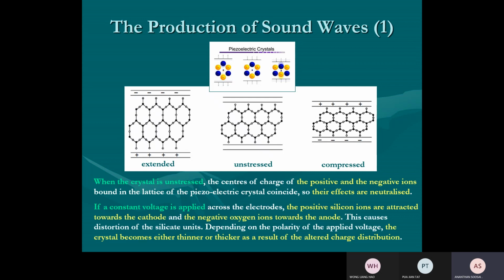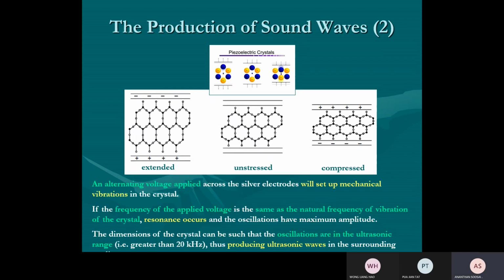These are altered charge distributions. So, in one word, you can say the crystal tends to oscillate when an electric field is applied. So the alternating voltage sets up mechanical vibration. The frequency of the applied voltage is the same as the natural frequency of the crystal. Resonance happens and produces ultrasound. Okay, it produces sound, sound which we can't sense, of course. It's ultrasound, a high frequency we can't sense.